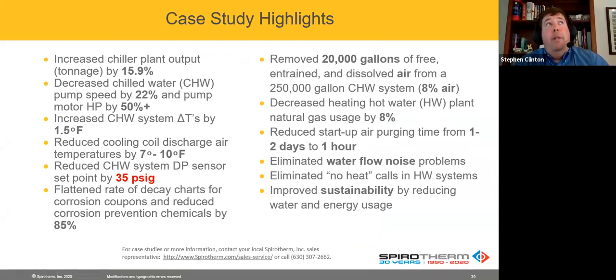Picked up chilled water plant capacity over 15% simply by removing air. Reducing pump speeds by over 20%, which is a cubed relationship to power. One of our universities, as I mentioned earlier, said they have reduced their DP, differential pressure on the chilled water system, by 35 PSI. So you see all these things.